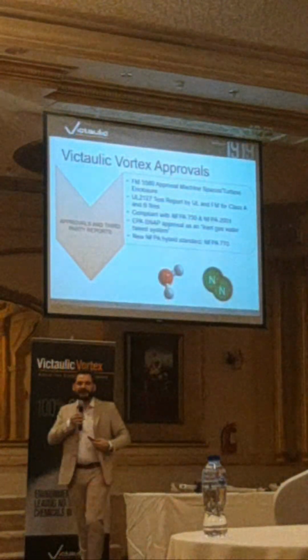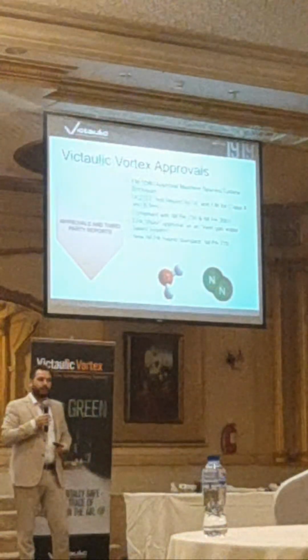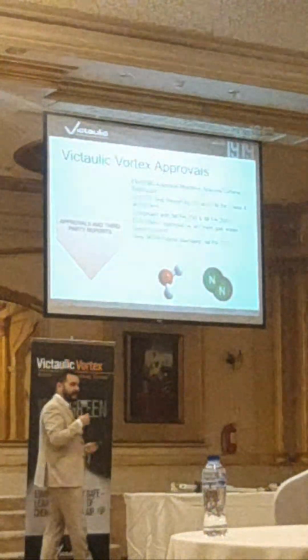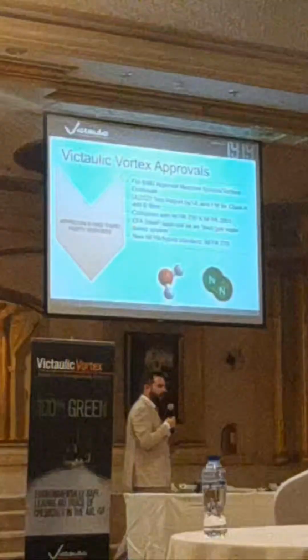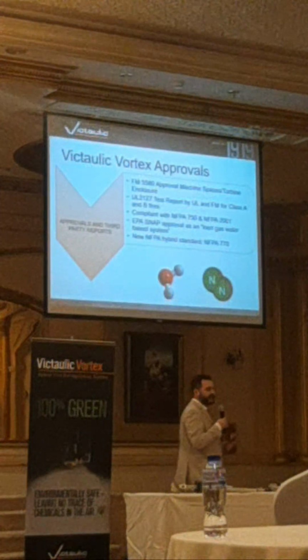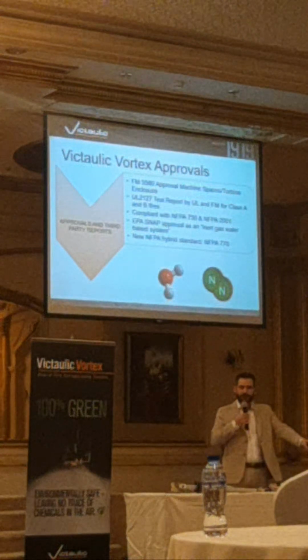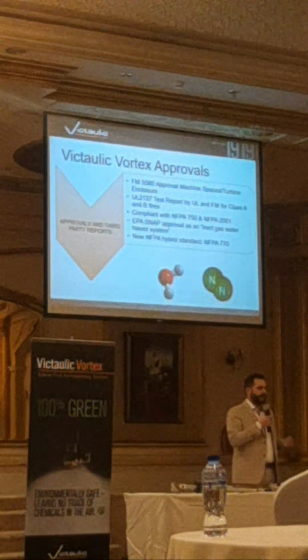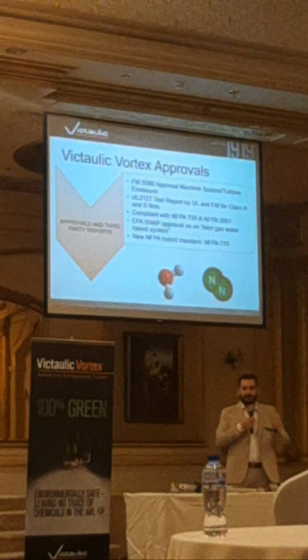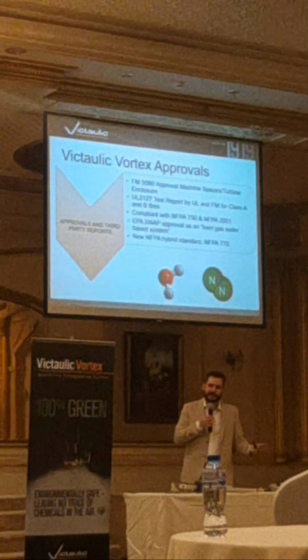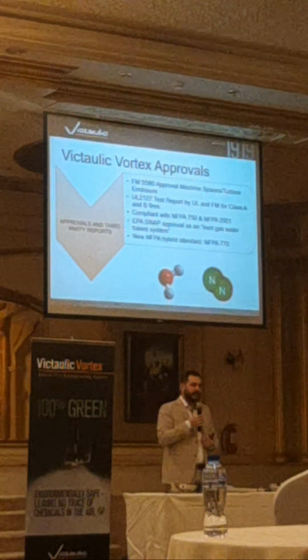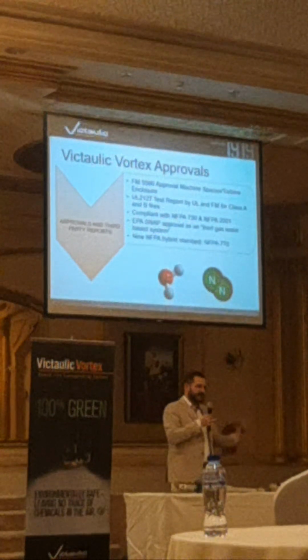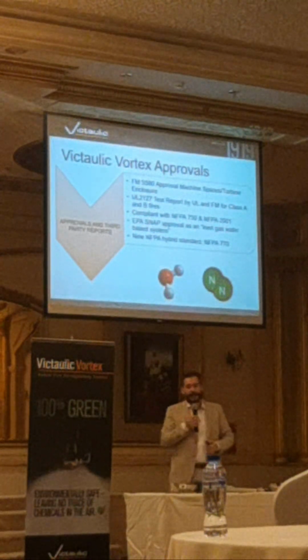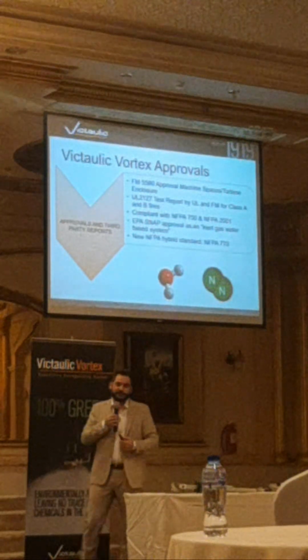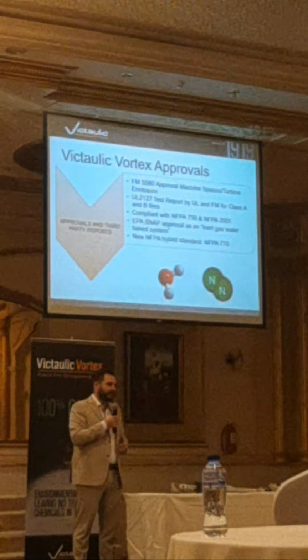An important one when it came to standards and approvals of the system: what Victaulic did, as we do for most of our products, is we contacted FM Global. We are still an American company, so that's the first point of contact that we had. There we said, okay, we have this new technology, this new system, how can we commercially bring it into the market? It is using two existing technologies, water mist and clean agent, but it is the combination of the two. And FM said, okay, fine, let's start testing against the water mist standard. They did all the testing, we were successful, and that's how we got the approval in 2008.